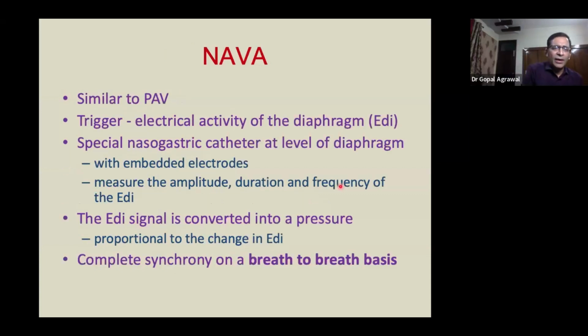There's also a newer mode called NAVA. There is an entity called electrical activity of the diaphragm. There's a nasogastric catheter at the level of the diaphragm through the esophagus, and that measures the activity of the diaphragm. Depending on the intensity of that activity, the pressure or volume of the breath delivered is proportionate to the trigger. So this is almost synchronized with the baby. Once the baby has some activity at the diaphragm, that trigger identifies it and the breath is delivered completely in synchrony. So NAVA is the completely synchronized mode of ventilation. The only disadvantage is it's not easily available, it's very costly, and it's not completely evidence-based. Evidence is coming up; probably in the next 5 years, we'll have more evidence on NAVA.